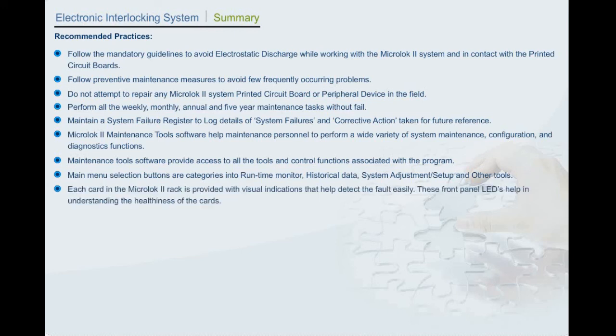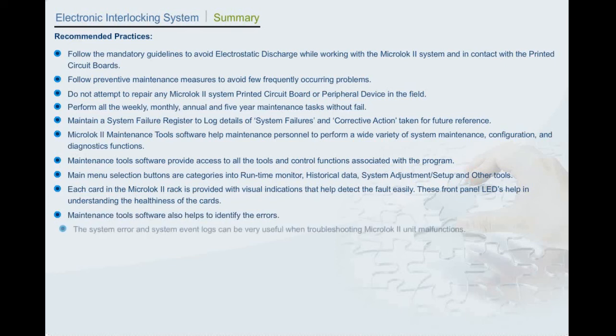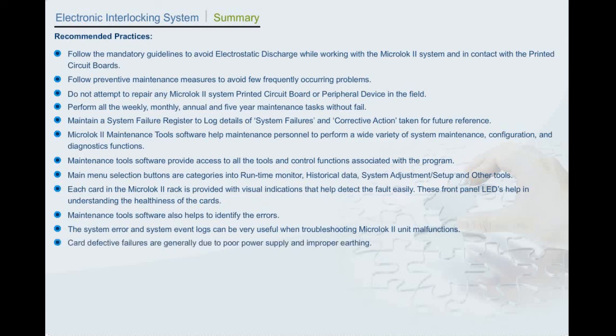Each card in the Microlok II rack is provided with visual indications that help detect the fault easily. These front panel LEDs help in understanding the healthiness of the cards. Maintenance Tools software also helps to identify the errors. The system error and system event logs can be very useful when troubleshooting Microlok II unit malfunctions.